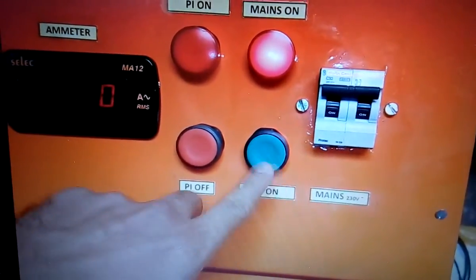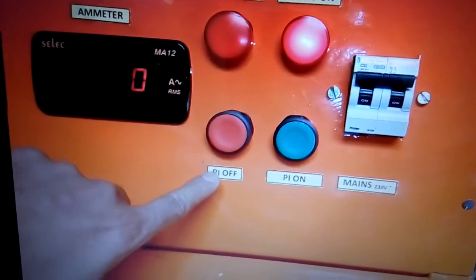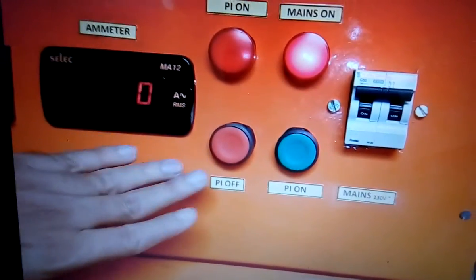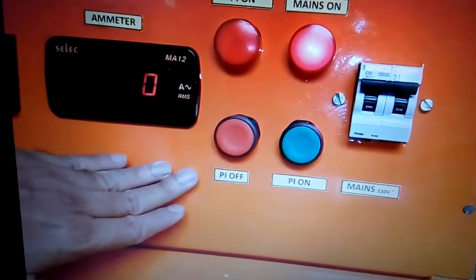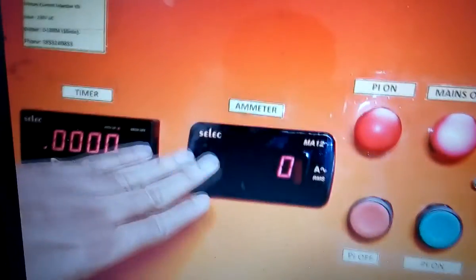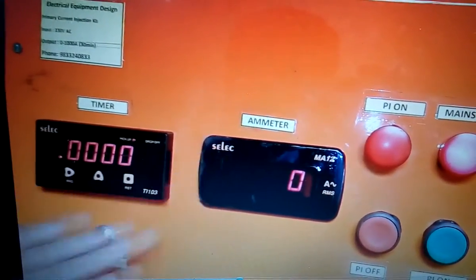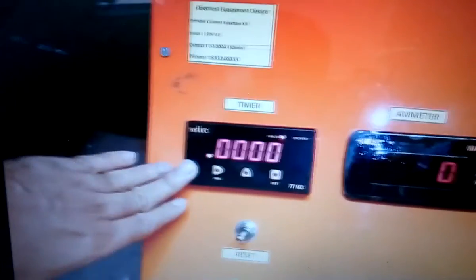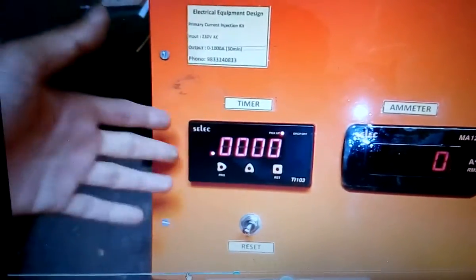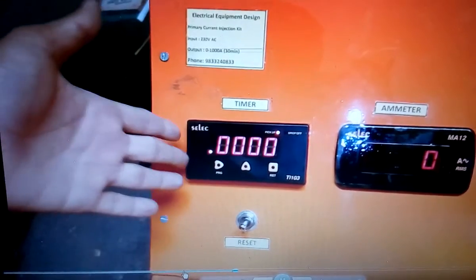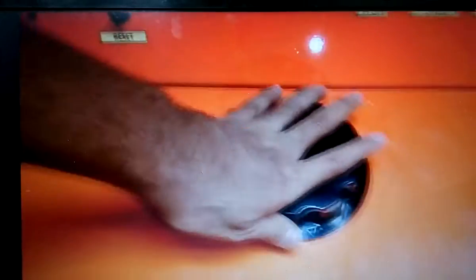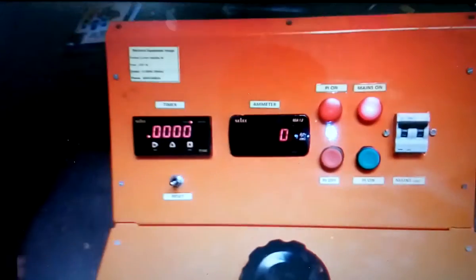This is PI on. Here you have to start the current injection procedure. This is PI off, so whenever you want you shut it off. And this is the ammeter. It will show what current is going through the apparatus. This is a timer. It will show you the time. This is a current controller. By varying the knob, you can vary the current from 0 to 1000 ampere in this case.